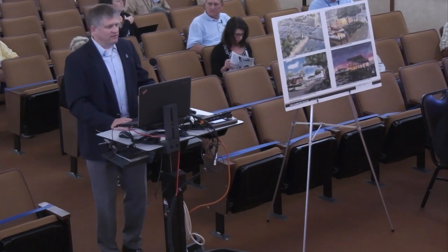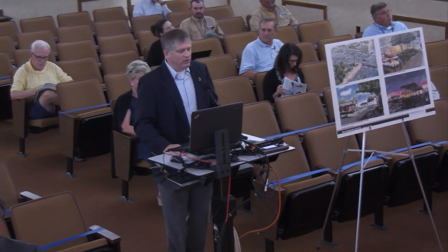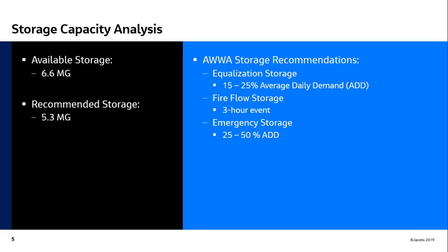One question we were asked was: does Fairhope have sufficient storage of potable water to meet their city size? Based on AWWA's recommendation, the city should have about 5.3 million gallons of storage, and you currently have 6.6. So unless we have an isolated issue with pressure in a part of town, you have adequate storage to meet AWWA's recommended storage for your system size, your fire flow and emergency storage.